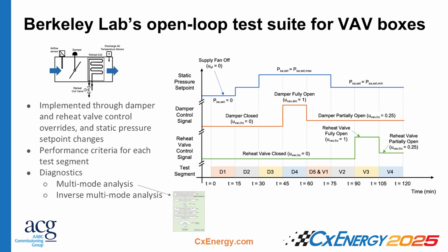In this case, we're looking at modulating the AHU fan up and down to elicit more airflow into a VAV. But the first part of this test is looking at modulating the damper position, closed and then fully open, to determine if there are any problems with the VAV damper. For instance, if the damper is closed and the supply fan is on, and you read airflow, then you may have a problem with a leaky damper. So that's the first half of the test.